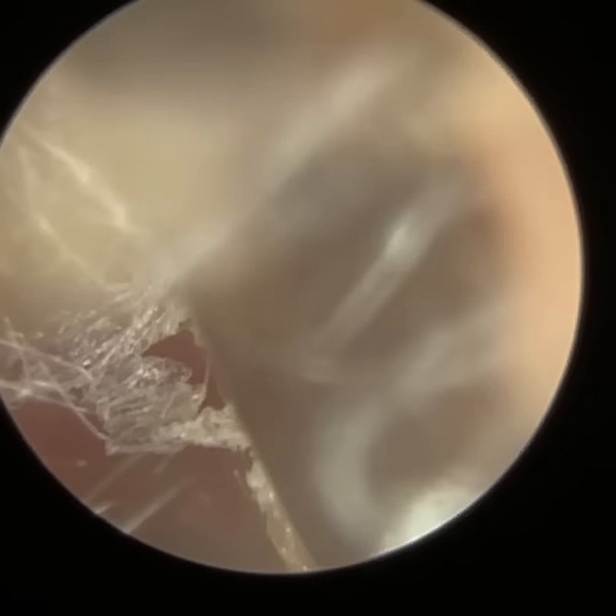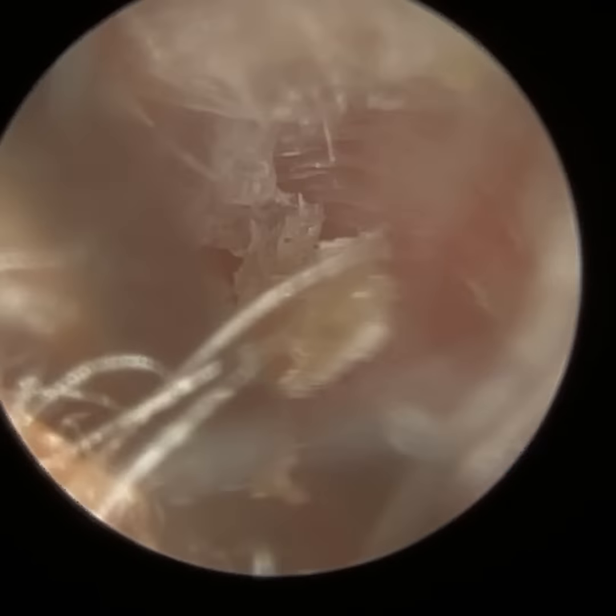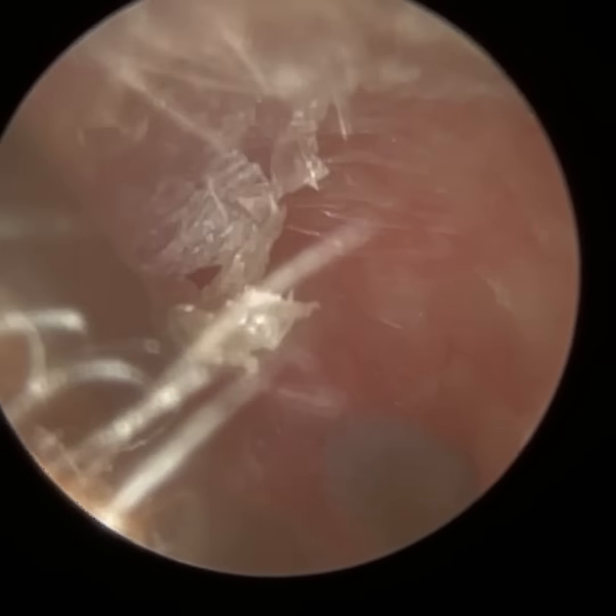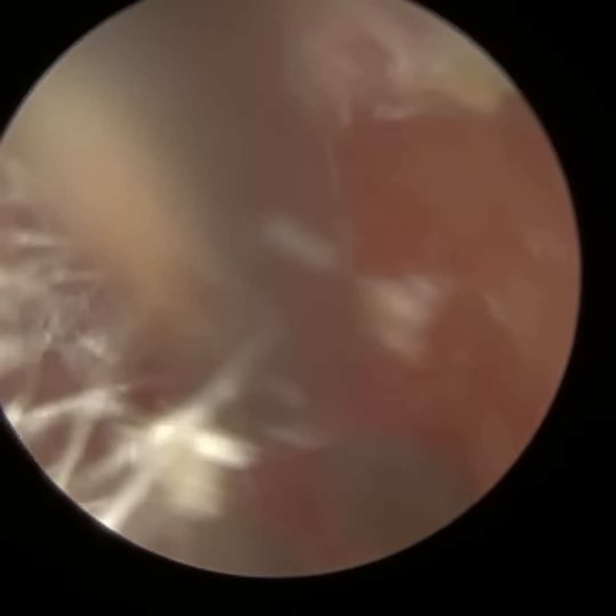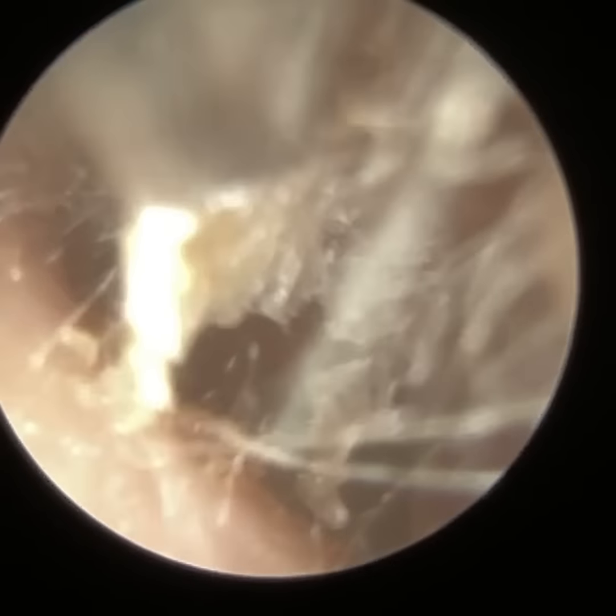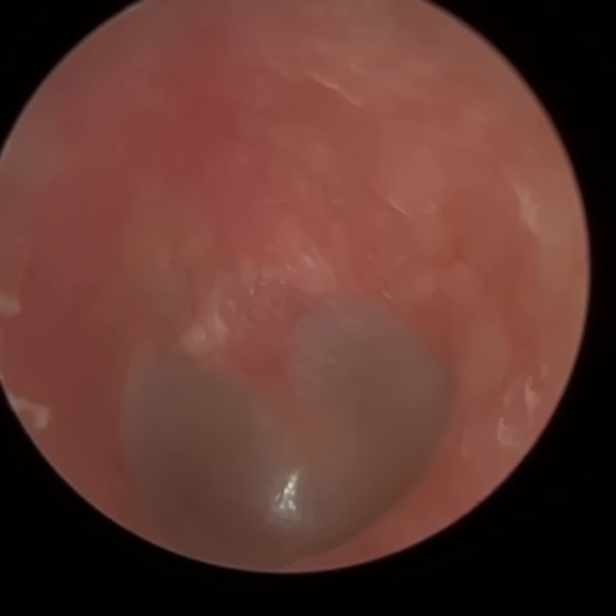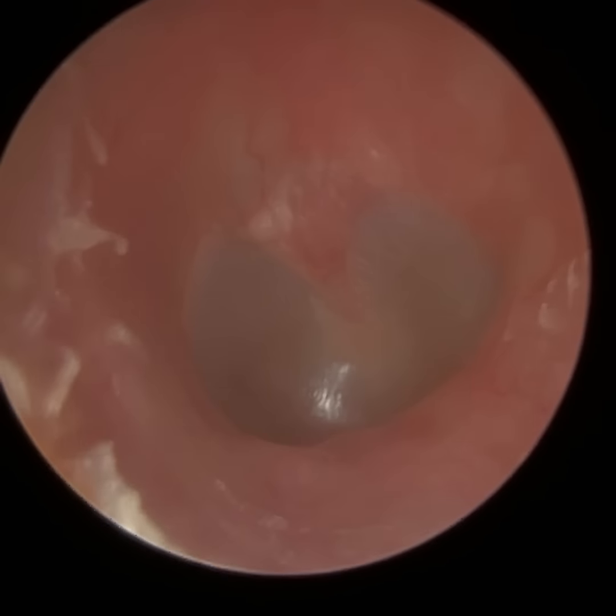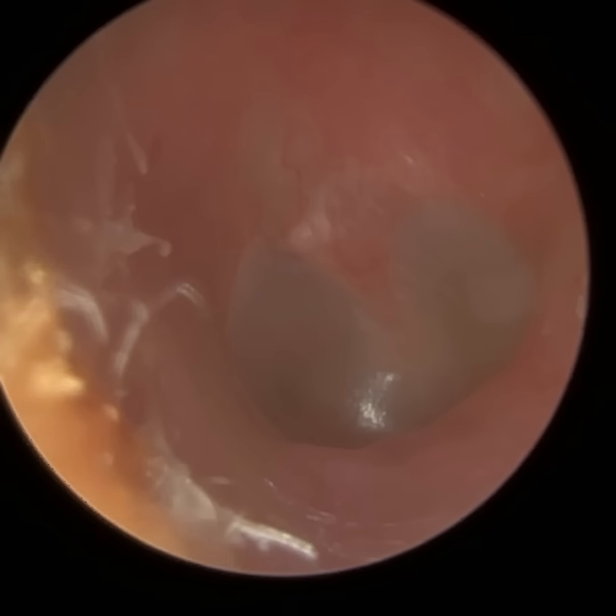And we're using the fine end suction probe here, so it really helps to minimize any clarinetting. So if anyone's new to the channel, when you suction dead skin, sometimes it can clarinet. And clarinetting is when the skin is just violently flapping at the tip of the suction probe, and it emits a very loud, high-frequency squeal. So I'm just having a real good nosy around here.